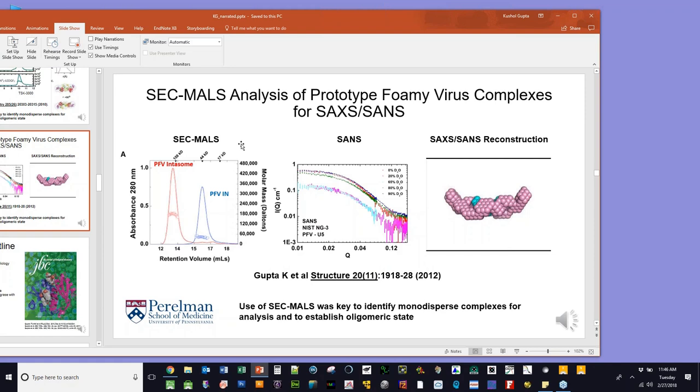Our mass calculations are very strongly reliant upon the refractive index of the macromolecule coming off the column. Usually for protein, this is very straightforward. It has a dn/dc of 0.183, 0.185. But for protein DNA complexes, that dn/dc figure actually becomes a little more complicated.